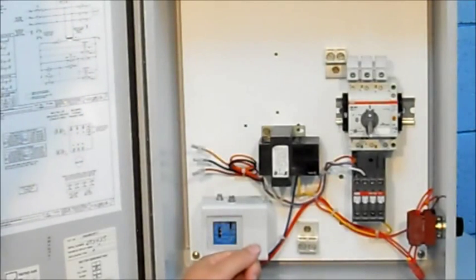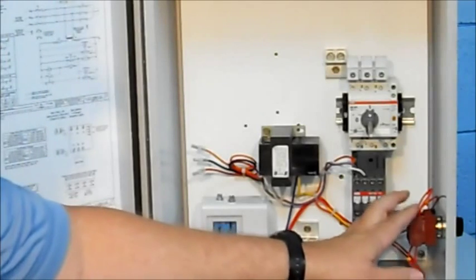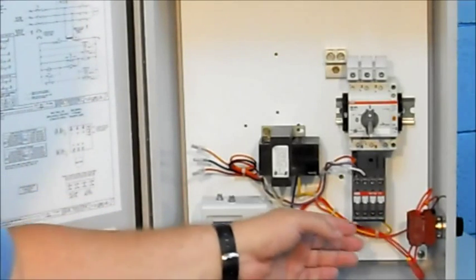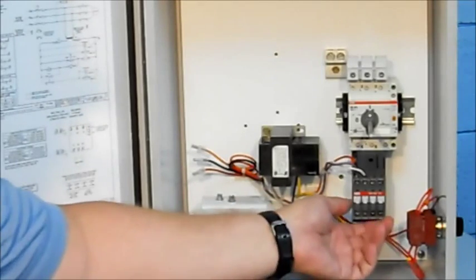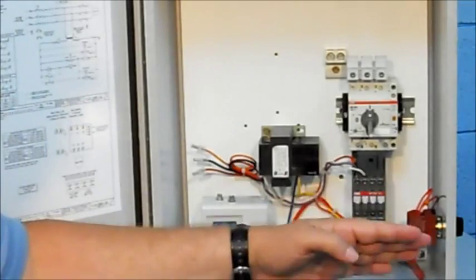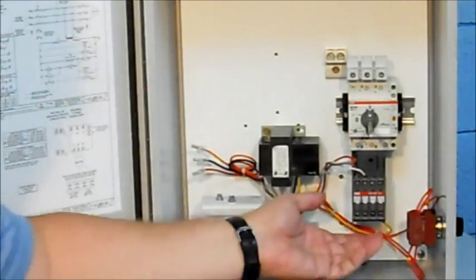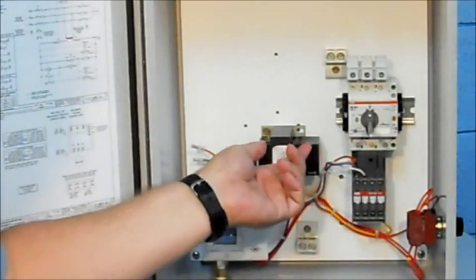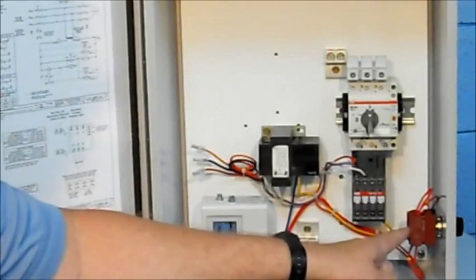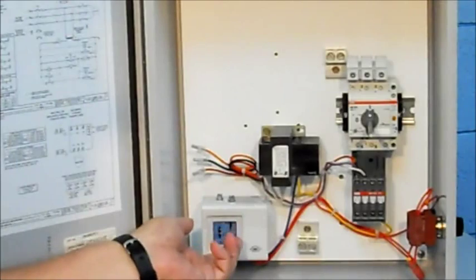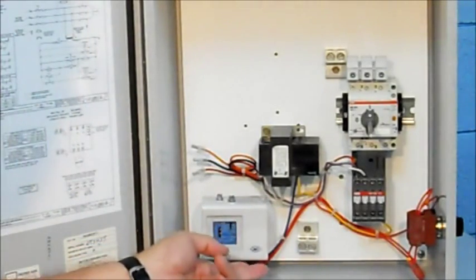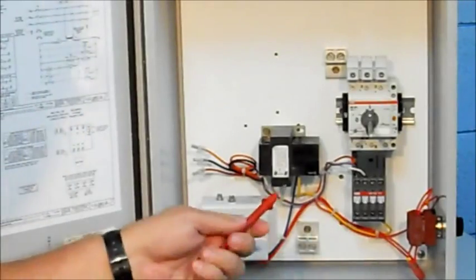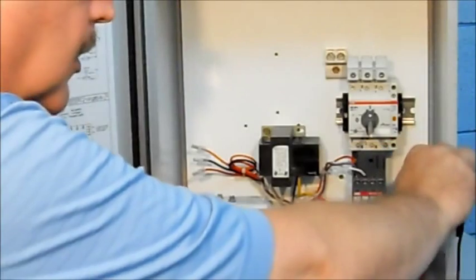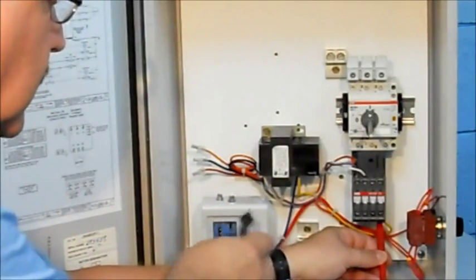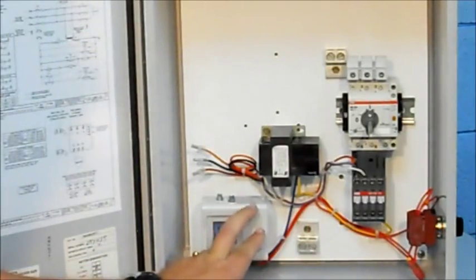Okay, now let's say that the pump does not run in automatic. Again, we go to the HOA selector switch, make sure we're in the auto position, and if we want to quickly check the coil and contactor, flip it over to the hand position. If it works in hand and doesn't work in auto, that tells us that the contactor and coil and transformer are good. It's between the auxiliary contact on the HOA switch and the pressure switch that's not making connection. So we follow those devices. We can actually measure our voltage both at the contact block on the HOA switch, as well as taking the cover off and measuring the voltage at the terminals inside the pressure controller.